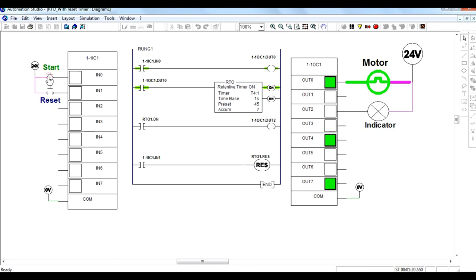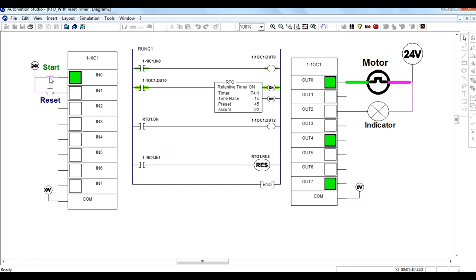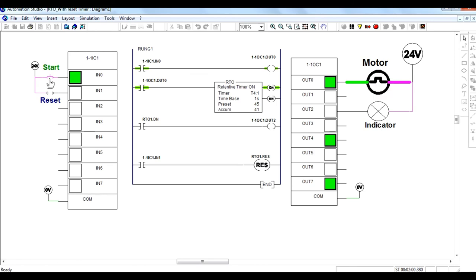The applications of retentive timers include monitoring the lifetime of any system. You can observe how much total time the system has been running, and after a certain period you can perform maintenance or change parts of the system. You can also fix an alarm instead of an indicator so that when the system lifetime reaches a particular time, the alarm turns on. Many applications can be made using the retentive timer.